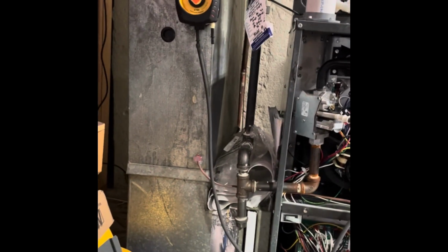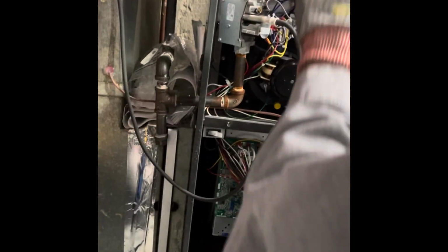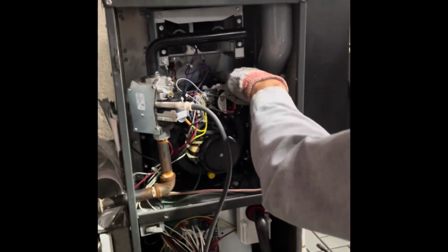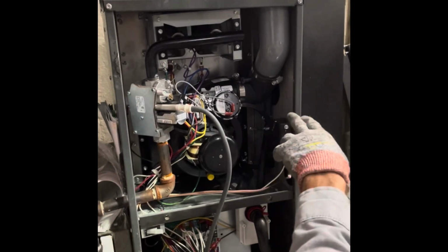This motor is probably going to be about 400. So now I confirmed his filter's in good condition. It's in the right way. I've got all my instruments hooked up. I've cleaned the burners. I cleaned the flame sensor. Once I get this furnace running, I'm going to be observing my number here.